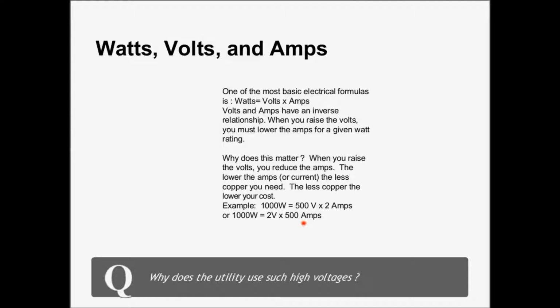You end up with 1,000 watts in both cases, but the larger amount of amps, the more copper you need, because you have to have a bigger wire to run the electricity through it. And as expensive as copper is, that's essentially why when you see pieces of equipment that use higher wattage, they will go with a higher voltage, so you don't end up with a wire the size of a fire hose. And it's really just all about cost. So, for example, anytime you go over 6,000 watts in UPS systems, they're almost always going to be 208 or 220 volts.